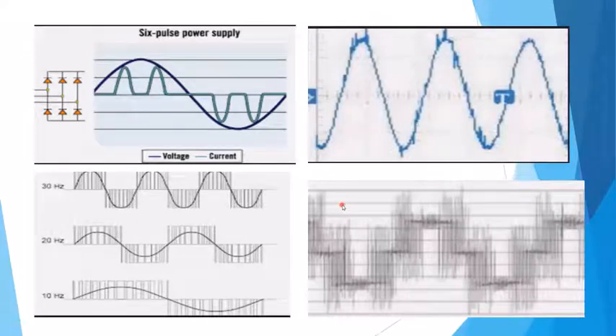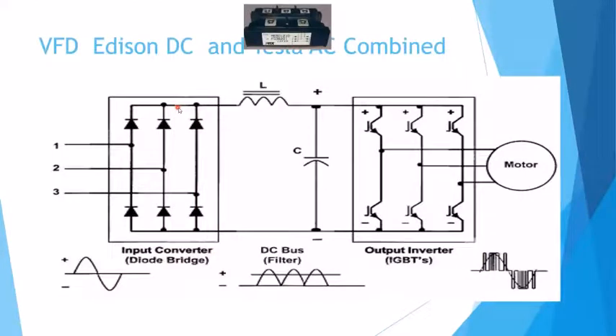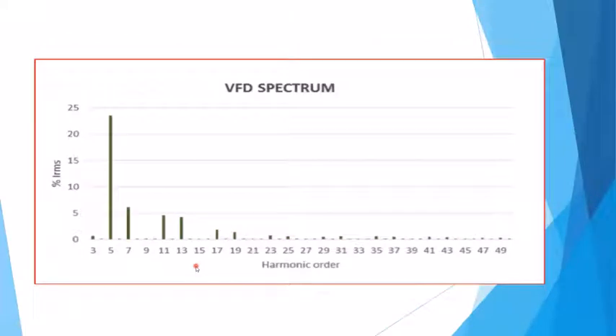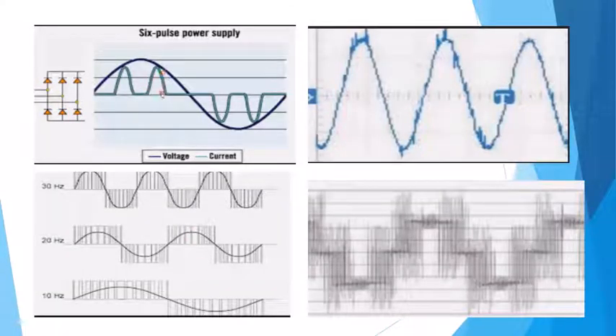So what I'm talking about is that, so you have your sine wave, which is your AC power here, and this shows the current waveform, and the current waveform will vary based off of where the load is and when these capacitors back here need to recharge and keep that DC to the right amount. So these will trigger and fire off of that sine wave, which is the actual AC power. You'll see the current flow that comes out of them is nonlinear, and so it's called nonlinear loads. What happens is that when you get this irregular harmonics and noise, if you look at an oscilloscope, you'll actually see the input voltage start chattering and having noise.